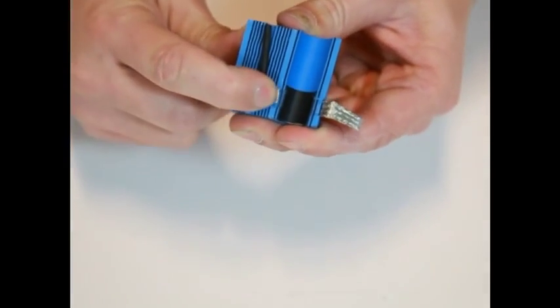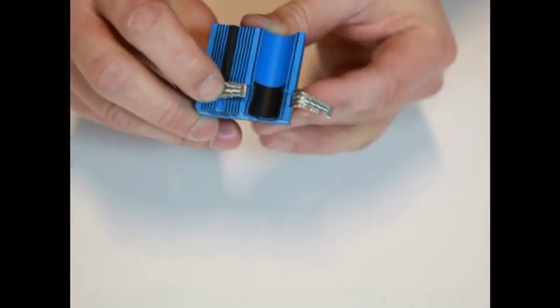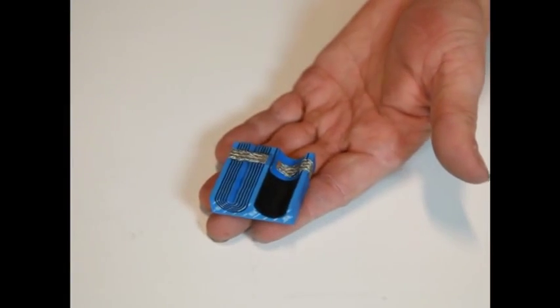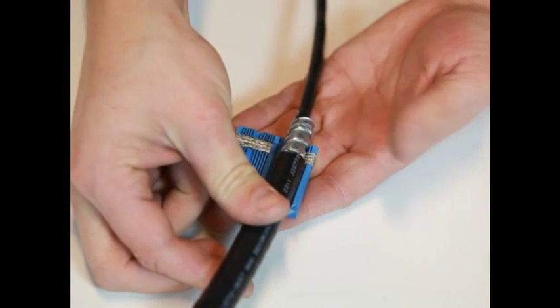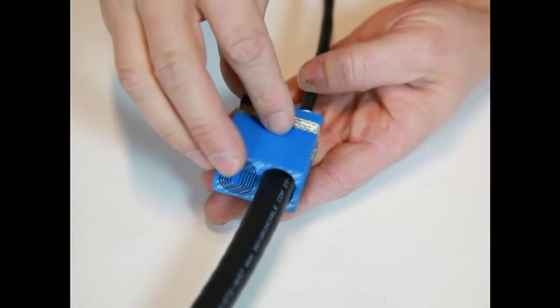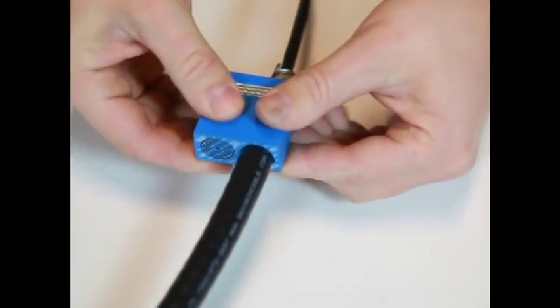Fold the braid tightly inside the module. There must be a 0.1 to 1mm gap between the module halves when fitting the cable.